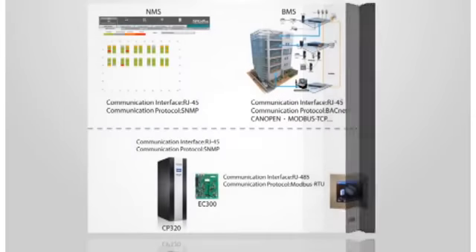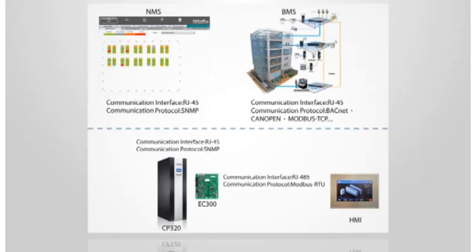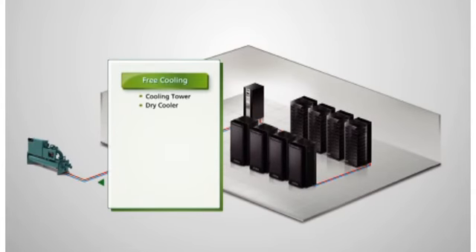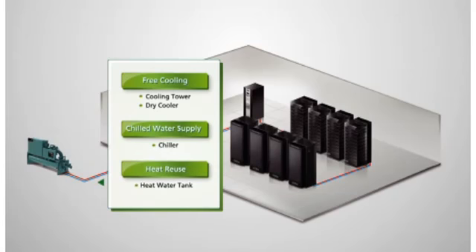The CDU supports SNMP and Modbus communication protocols, allowing infrastructure administrators to access CDU status information through a building's central monitoring system. A10 CDU has the flexibility to support either type of primary loop water system found in a building, free water cooling or chilled water supply.